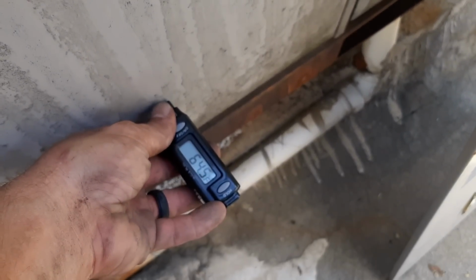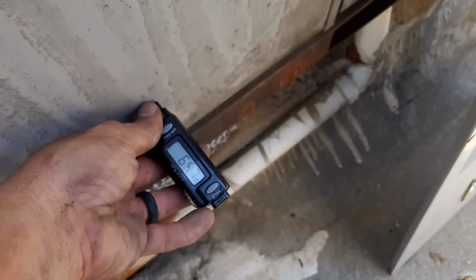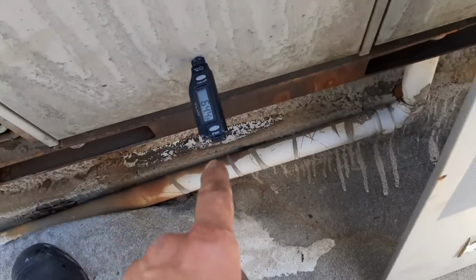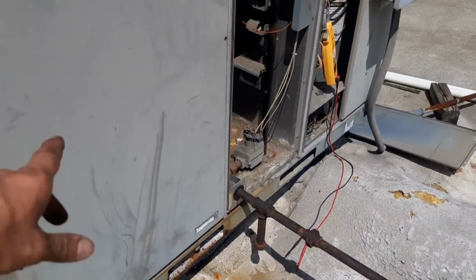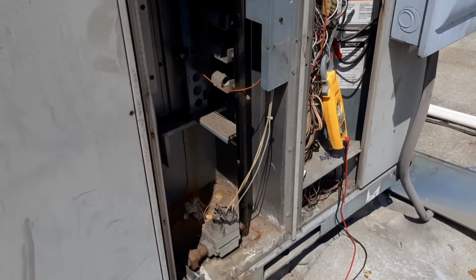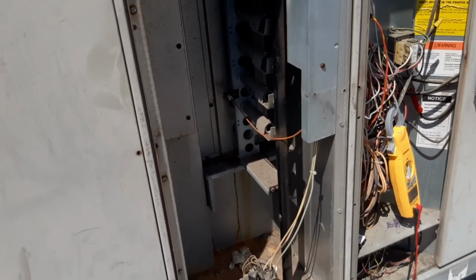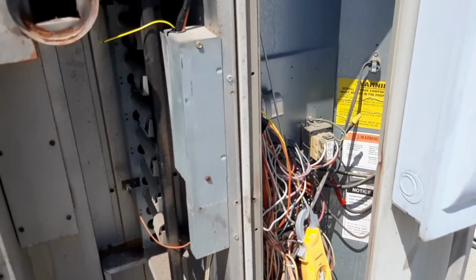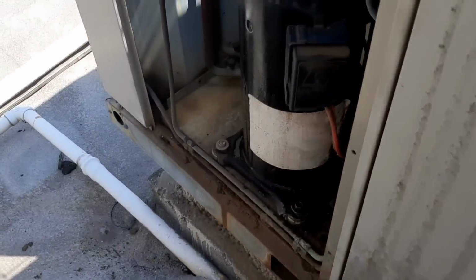So I'm running about 84 degrees in the space, 84, so I'm at 64, which I would expect - it's still coming down. I would expect it to be higher than normal because of my filters and just airflow in general. Of course the belt was a little bit smaller that I put on, so we're gonna get the right size belt anyways. Now that I know everything's gonna run, we'll get filters and a belt for it, and it ought to be okay.